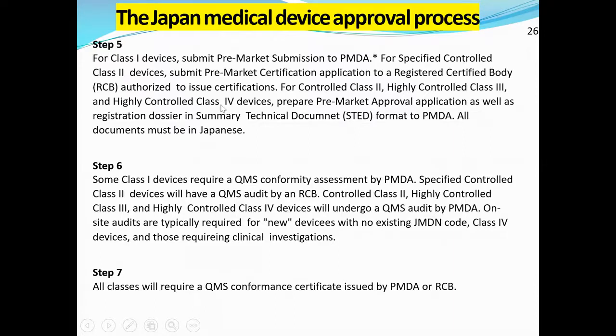So that is why it's very difficult to crack this Japanese approval, and you have to appoint the agent who will do all these things. You have to give your documentation in English, get it translated into Japanese, and he will be the local point of contact with the health authority for getting our marketing approval for medical devices which fall under category 1 to 3. Some class 1 devices require QMS conformity assessment by PMDA. Specified controlled class 2 devices will have a QMS audit by RCB, and controlled class 2, highly controlled class 3 and highly controlled class 4 devices will undergo a QMS audit by PMDA.